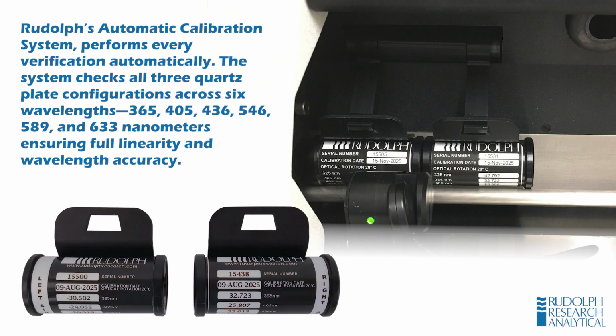Rudolph's automatic calibration system performs every verification automatically. The system checks all 3 quartz plate configurations across 6 wavelengths: 365, 405, 436, 546, 589, and 633 nanometers, ensuring full linearity and wavelength accuracy. The entire process is managed by the instrument, so operators can start calibration and continue other work.